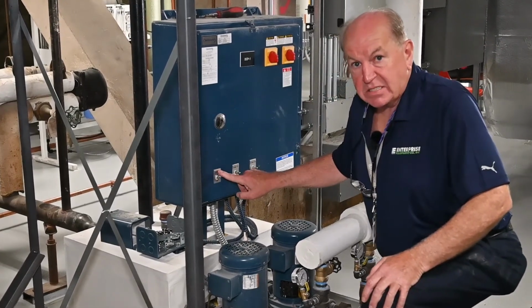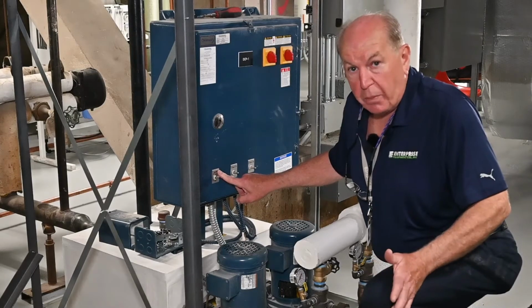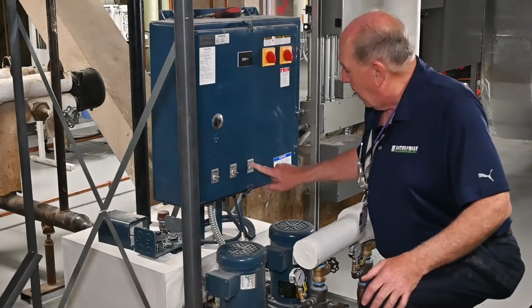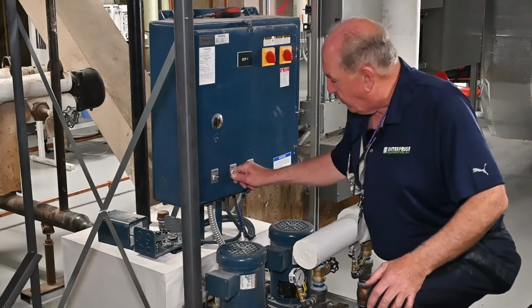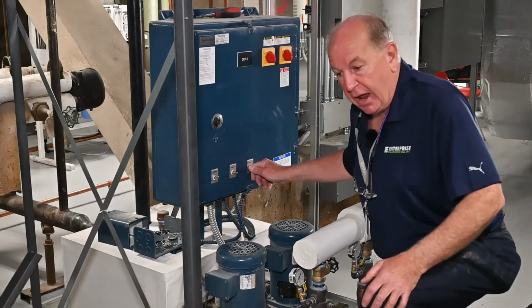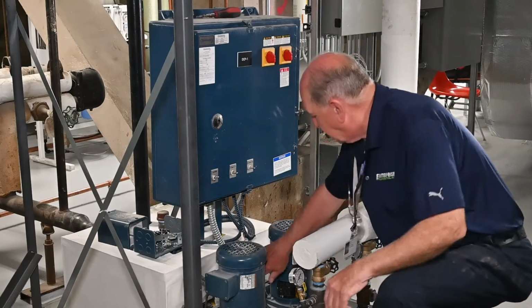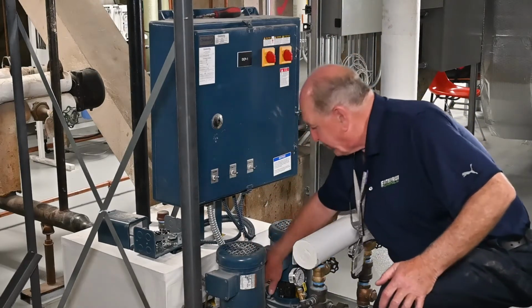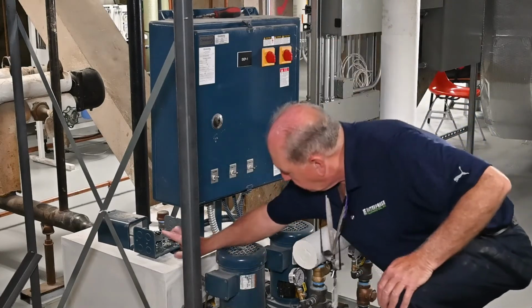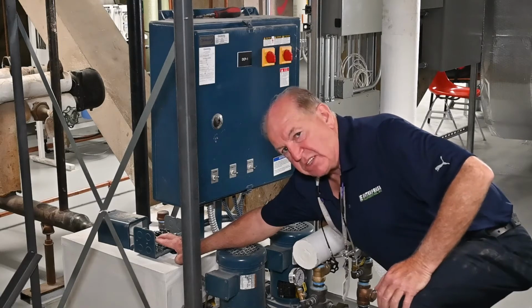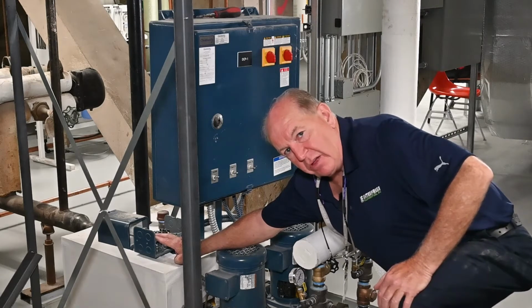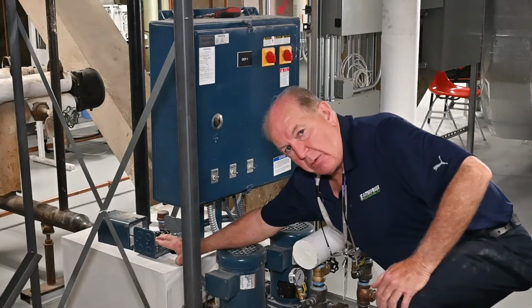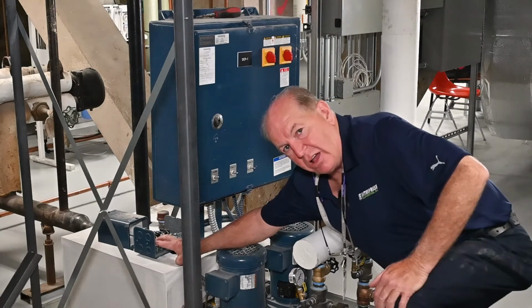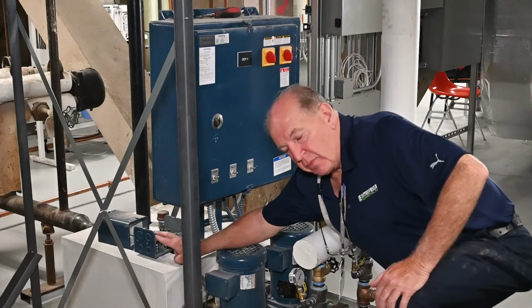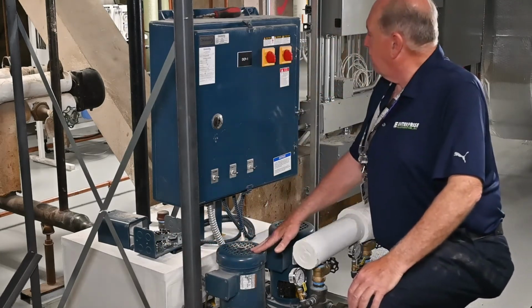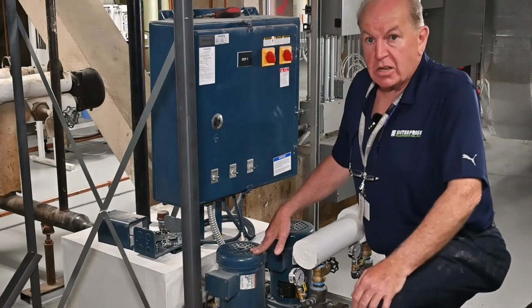That alarm switch usually stays up in the on position, so it will buzz if there is a problem. Both pump switches stay in the automatic side. There's a hand-off-auto, but you'll leave them in automatic. And there's a sight glass here. So about halfway is where the float will turn on the first pump. And typically, if things are normal, that pump will come on and off. If for some reason that first pump doesn't come on, the water level becomes higher, and it turns on the second pump. And that's basically it. It's a duplex condensate pump.